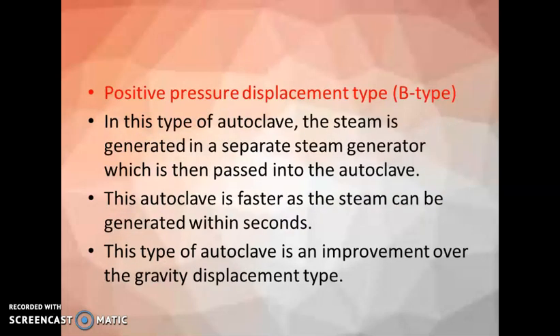Next is the positive pressure displacement type or B type. In this type of autoclave, steam is generated in a separate steam generator, which is then passed into the autoclave. This autoclave is faster as the steam can be generated within seconds. It is an improvement over the gravity displacement type. This is a much more advanced type.